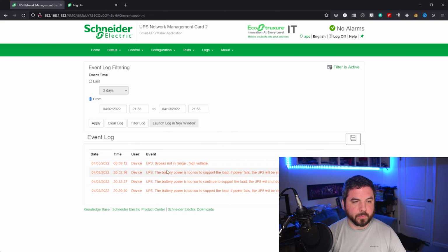These other errors have come from the original installation of the UPS. I had actually not realized that you had to run the battery calibration multiple times before it would register how much time was left. So please make sure you do that when you set up your UPS, especially with new batteries, and you'll make sure that you register the proper usage, the proper time remaining on your batteries.